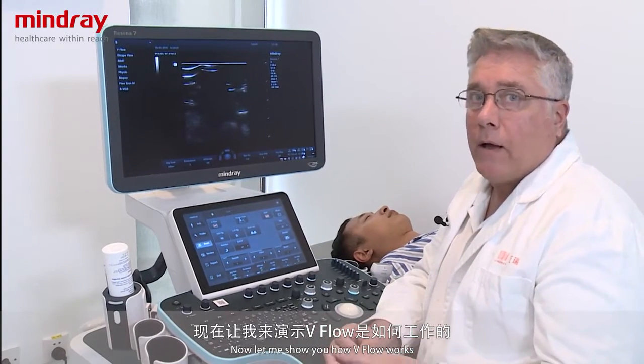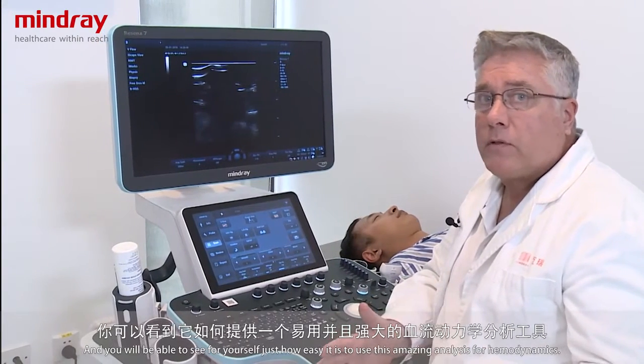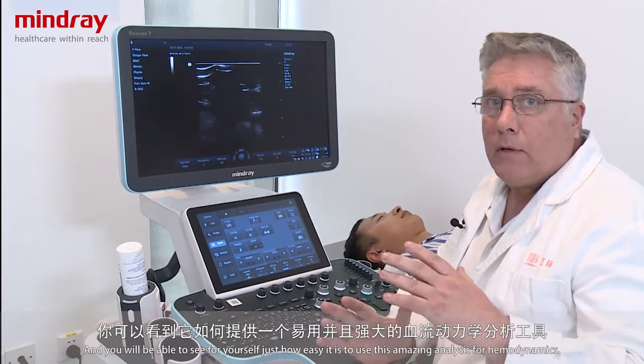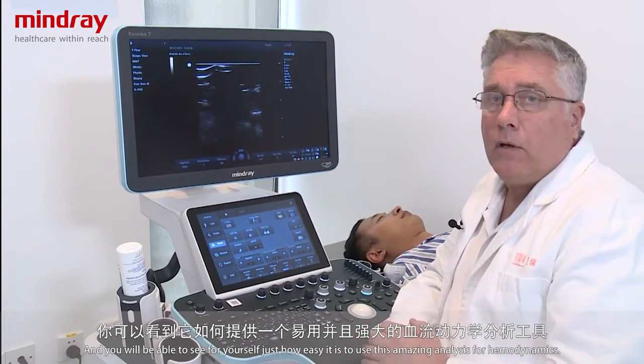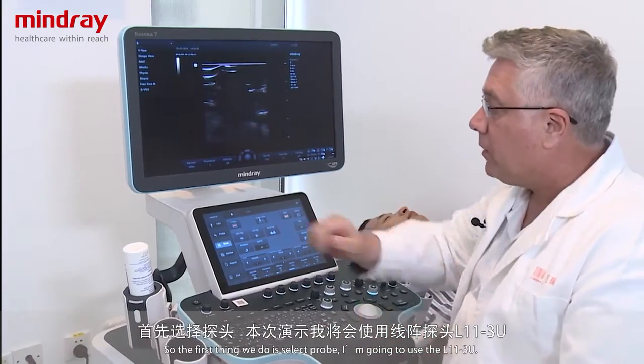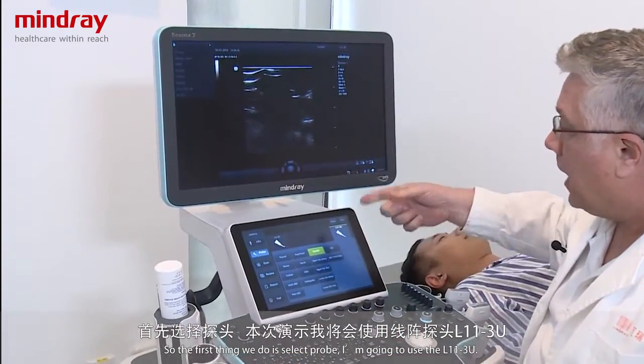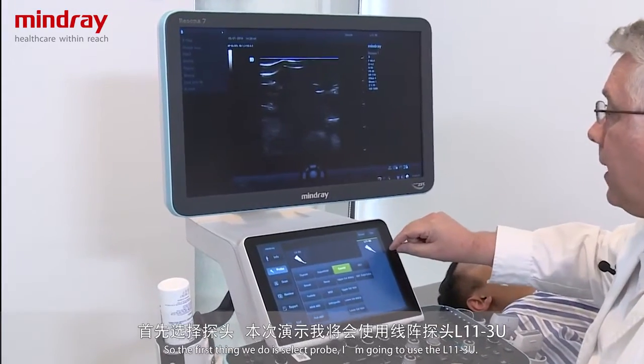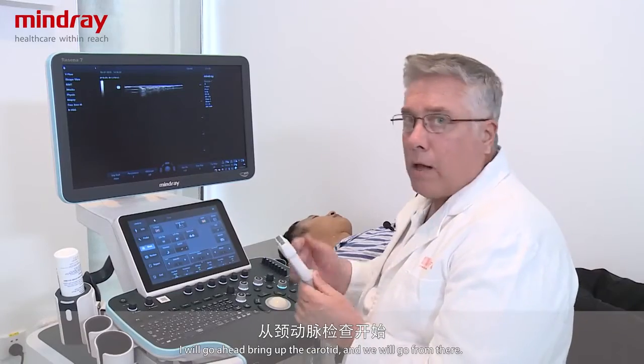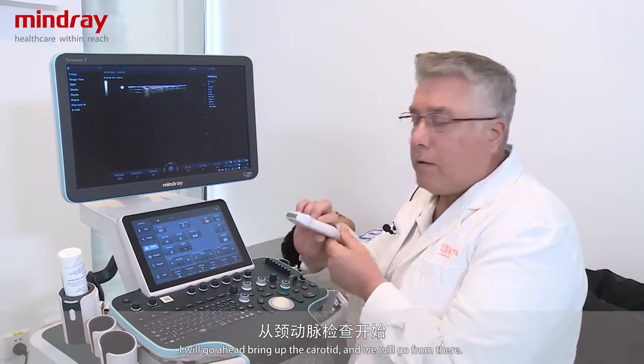This will lead to more accurate measurement and analysis for vascular studies. Now we're going to show you exactly how V-flow works, and you'll be able to see just how easy it is to use this analysis for hemodynamics. The first thing we do is select a probe — I'm going to use the L11-3U — and bring up a carotid image.